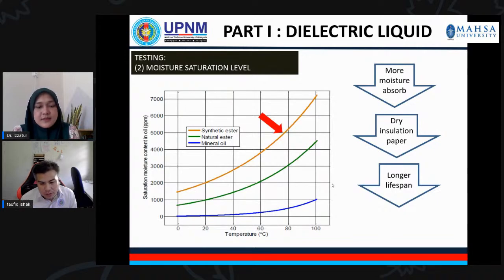When you have a high water saturation level, it will help to keep your cellulose insulation material dry. And of course, when the insulation material of your transformer is dry, it can extend the life of the transformer, especially the paper and also the pressboard of the transformer. So more moisture absorbed means dry insulation paper, and also a longer lifespan of your transformer.